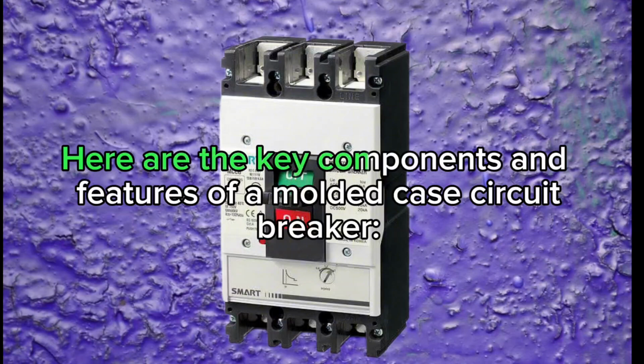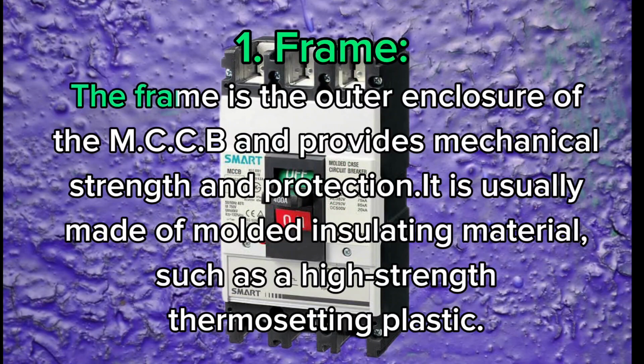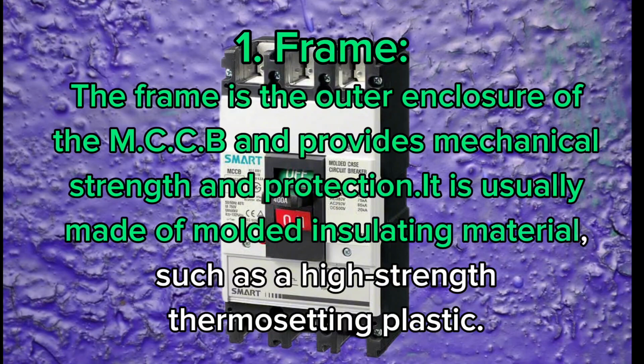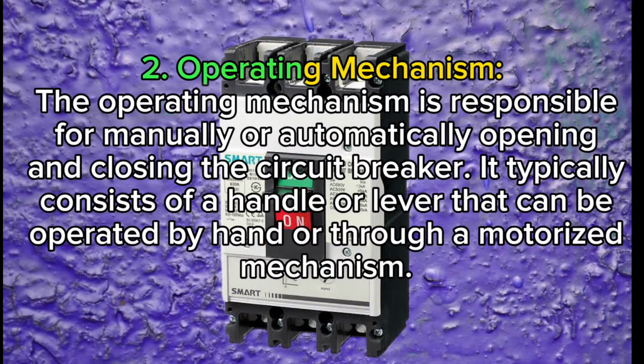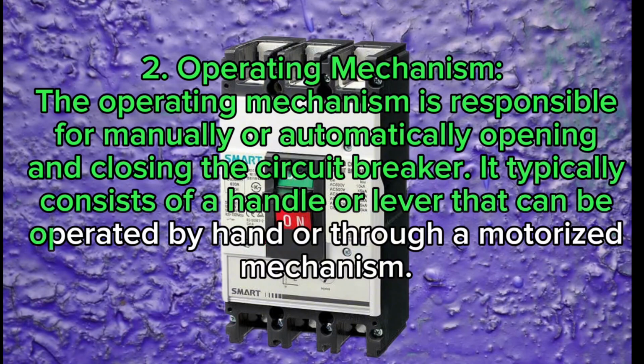Here are the key components and features of a molded case circuit breaker. 1. Frame. The frame is the outer enclosure of the MCCB and provides mechanical strength and protection. It is usually made of molded insulating material, such as a high-strength, thermosetting plastic. 2. Operating mechanism. The operating mechanism is responsible for manually or automatically opening and closing the circuit breaker. It typically consists of a handle or lever that can be operated by hand or through a motorized mechanism.